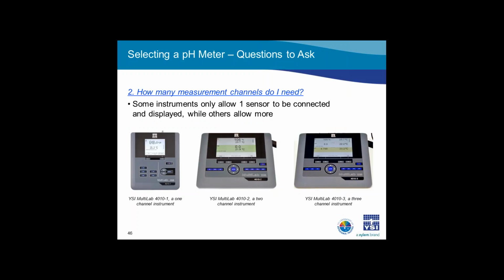The next question to ask is the number of measurement channels you would like. A measurement channel is basically an input for a sensor, so one measurement channel instrument will only allow one sensor to be connected, and one measurement will be displayed on the instrument in addition to temperature. The Multilab 4010-3 is a 3-channel instrument, so the user can connect 3 different sensors, such as a pH sensor, a dissolved oxygen sensor, and ammonia sensors.